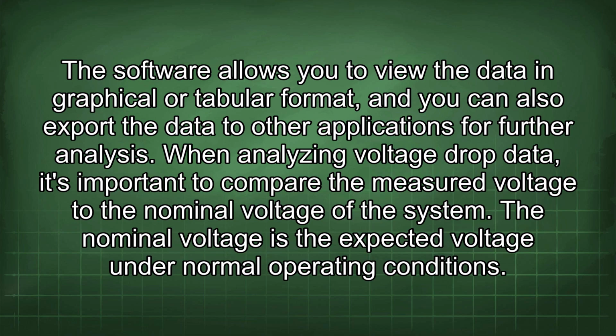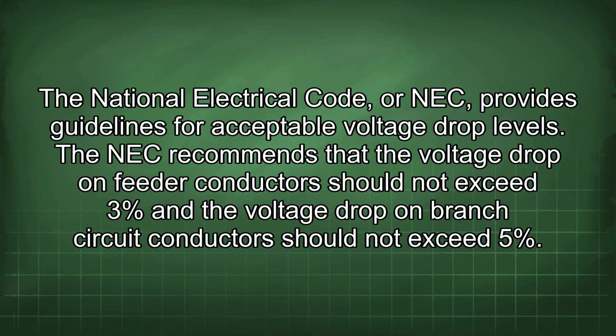When analyzing voltage drop data, it's important to compare the measured voltage to the nominal voltage of the system. The nominal voltage is the expected voltage under normal operating conditions. The National Electrical Code, or NEC, provides guidelines for acceptable voltage drop levels. The NEC recommends that the voltage drop on feeder conductors should not exceed 3% and the voltage drop on branch circuit conductors should not exceed 5%.